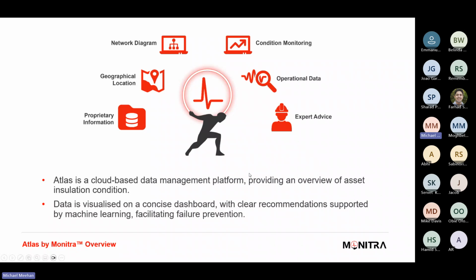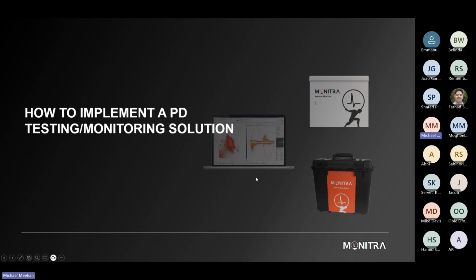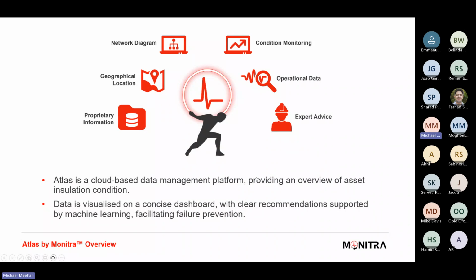So in terms of how to implement a PD testing solution, we talk about measuring PD and we talk about testing, but what does it look like? Obviously, you've got a HV machine, it's high voltage. If we're talking about online in particular, how do you actually measure a high voltage system? How do you do that safely?